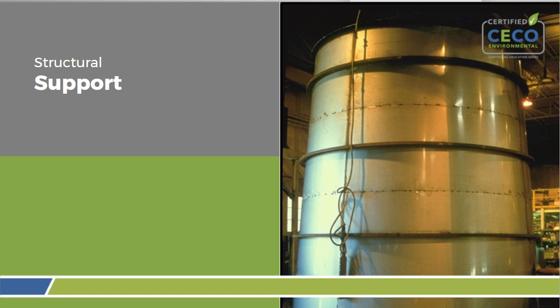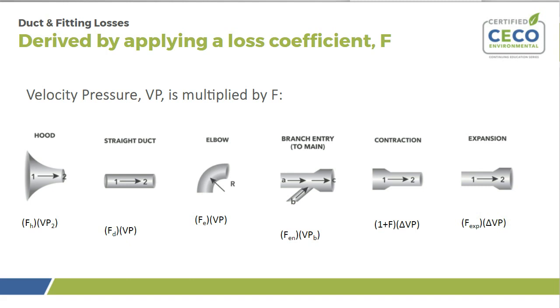The losses that you have in all of your ductwork components are expressed in an F, or a loss coefficient, and they're always multiplied by velocity pressure to get the loss in inches of static pressure. We call them loss. It's actually the energy that you need in the system to convey material properly. For a hood, the loss is what it takes to accelerate the air from 0 outside of the hood up to conveying velocity at point 2. And hoods are also dependent upon the shape.